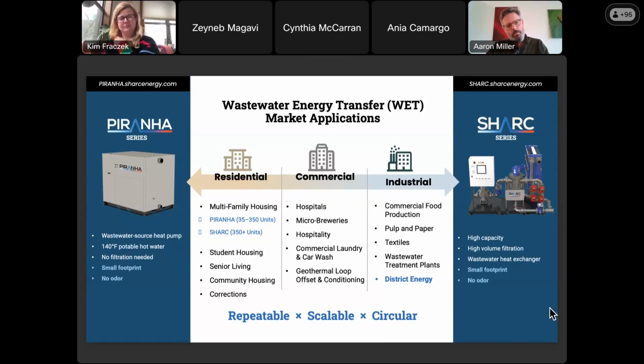For multifamily residential buildings, the Piranha is really a water-to-water heat pump. We're basically harvesting energy from water to make potable hot water, just using a different type of energy source. We've got a tank inside that allows us to fill it with that 70-some-odd degree wastewater and slowly extract the energy over the day, put it into a refrigeration cycle, move it through a potable heat exchanger, and give you 140 degree hot water all day, every day.